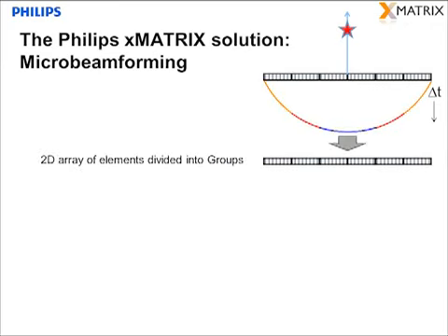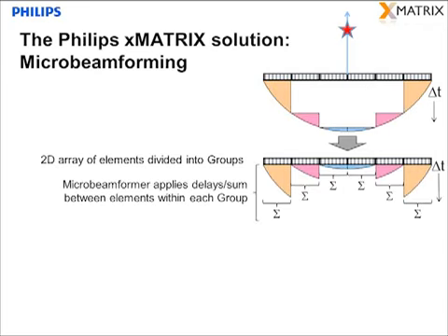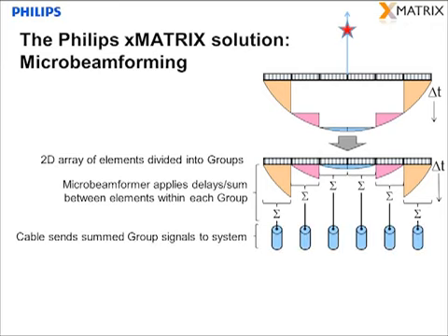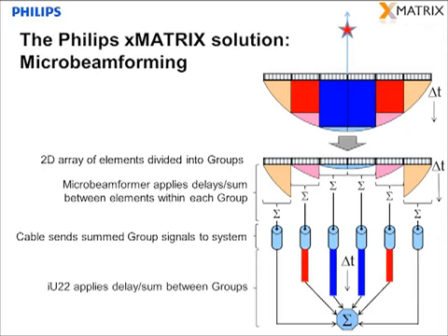We start by dividing the array of elements into groups. There are 6 groups in this example. The colors indicate how segments of the delay curve correspond to the groups of array elements. The microbeamformer in the xMATRIX transducer applies delays to elements within each group and sums together the signals from elements within each group. We then send the summed group signals down the cable to the ultrasound system. The ultrasound system then applies additional delays between groups and sums the resulting signals together.